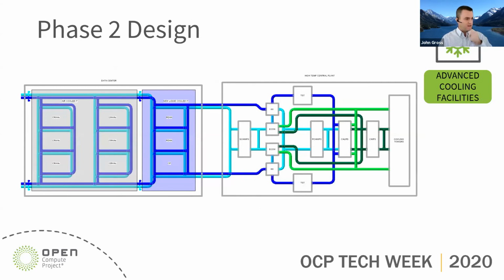So this is the high level schematic of what we ended up with. The other part I wanted to bring into this conversation, and why we went full bore with the separate chiller plant, not just separate chiller loops and a dry cooler and evaporative cooler solution, is that we found out during the investigation that the campus chiller plant, while it was originally designed to be concurrently maintainable, through some uninformed value engineering exercises within that project's construction, without consultation with the data center design team, was actually built not concurrently maintainable. We found a number of single points of failure. So we designed this chiller plant to be the primary source of cooling to the HPC, but also to serve as the +1 to the air-cooled enterprise data center.